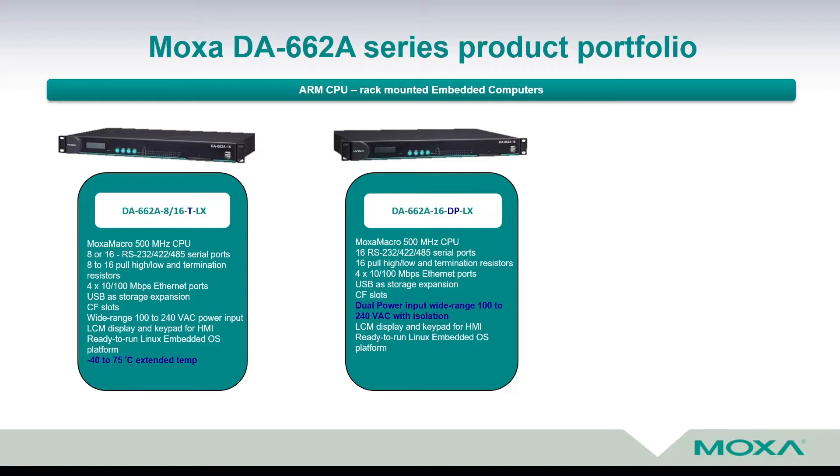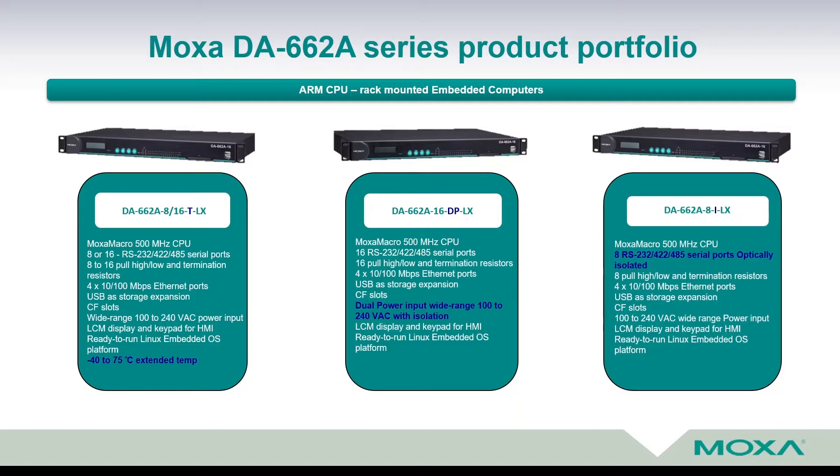This device comes with 16 serial ports. And the third device is DA662A-8, meaning 8 serial ports, with -I indicating optically isolated serial ports, and -LX. No matter which of these three variants, they are hardware the same, running Moxa's CPU at 500 MHz, and featuring from 8 to 16 serial ports, including termination and polarization resistors for RS422 and RS485 bus.